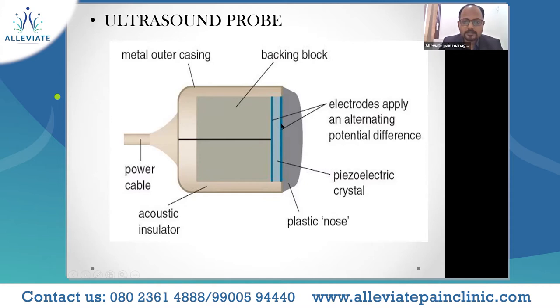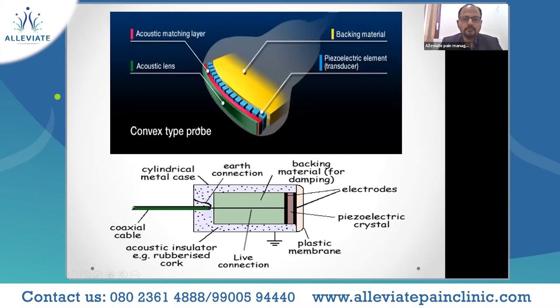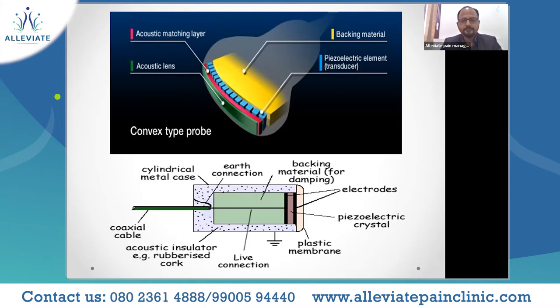The energy must be contained within the device, which is why you have the acoustic insulator, metal outer casing, and backing block, as well as the plastic nose to help in smooth scanning. At the tip of the transducer, there is the array of crystals covered by an acoustic matching layer, then the backing material, and the acoustic lens which is used to magnify the sound waves produced.